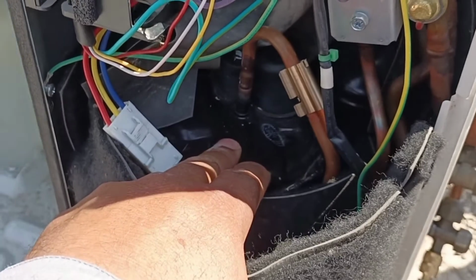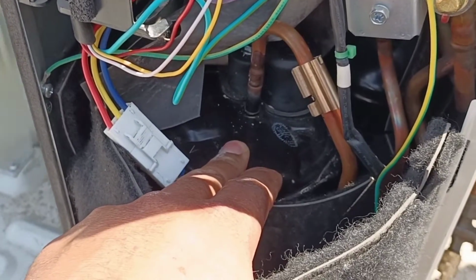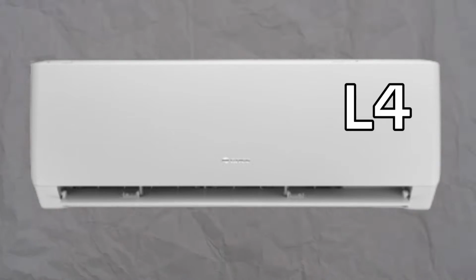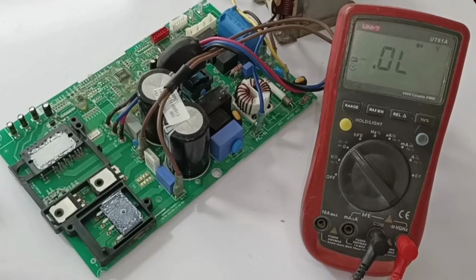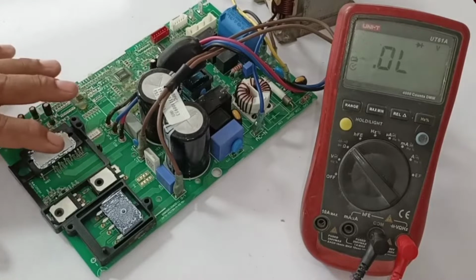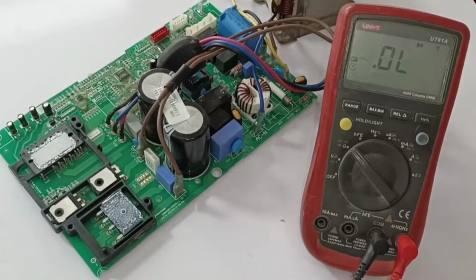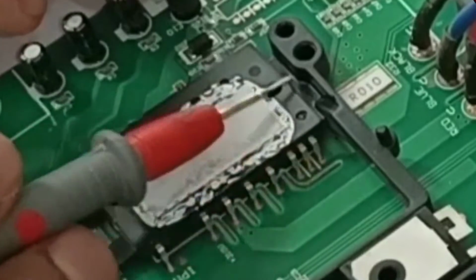When the compressor in your inverter mini split air conditioner does not start, then the L4 error code will be displayed in your air conditioner due to the drive circuit not working. This was the explanation of this error code. This IPM is responsible for driving the compressor.